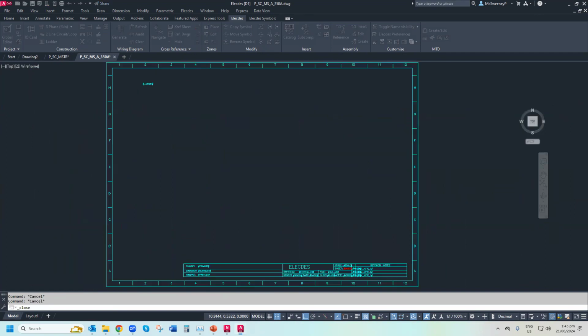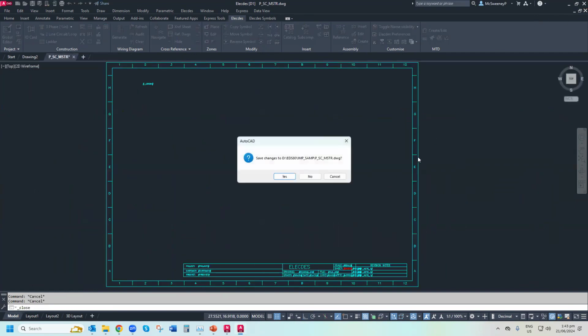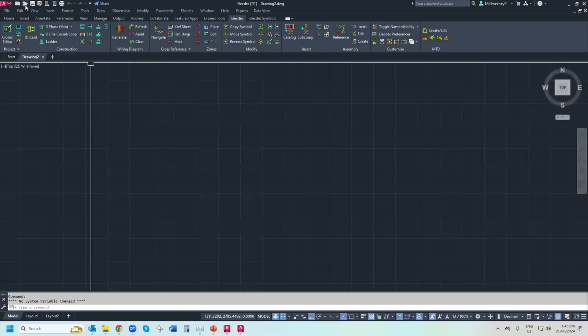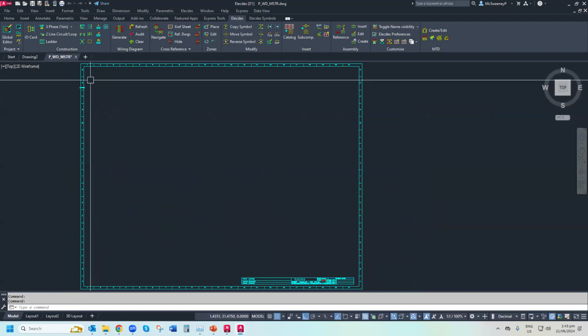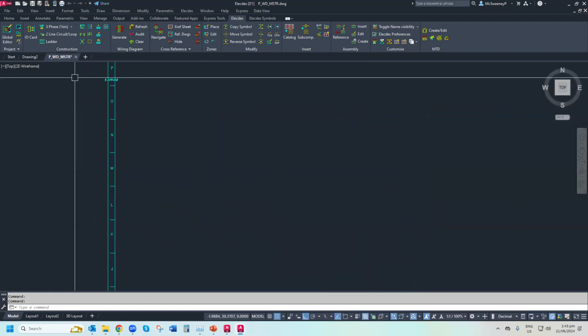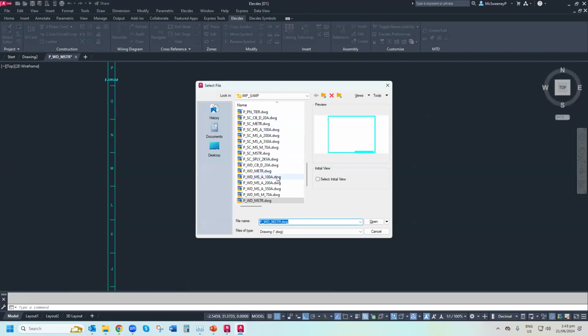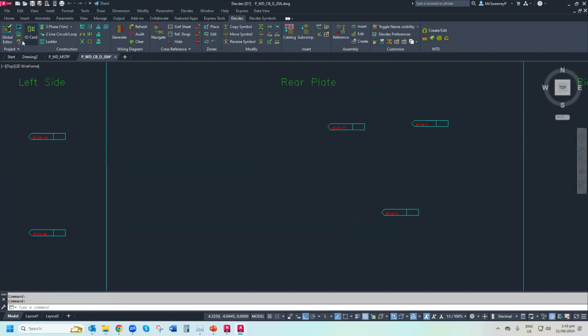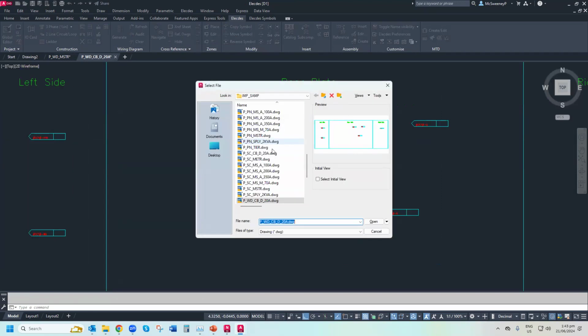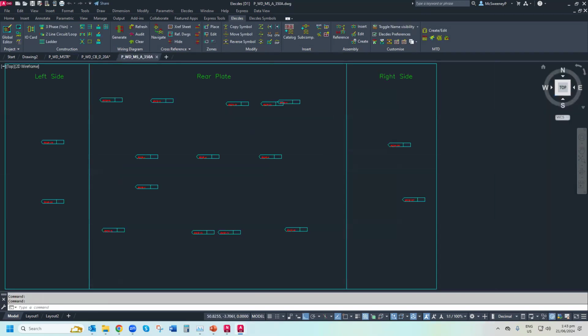And then the only other thing that I wanted to show is we automatically generate wiring diagrams, and we've actually set up wiring diagram place markers as well. So if I have a look at my wiring diagram master, I can see there's my #origin. And again, there's my wiring diagram 20, and these are the little place markers. And again, I'll cycle through them: metering, 100 amps, 200, 350, 70 power supply. But let's open up the 350. You can see it's got a lot more markers in there.